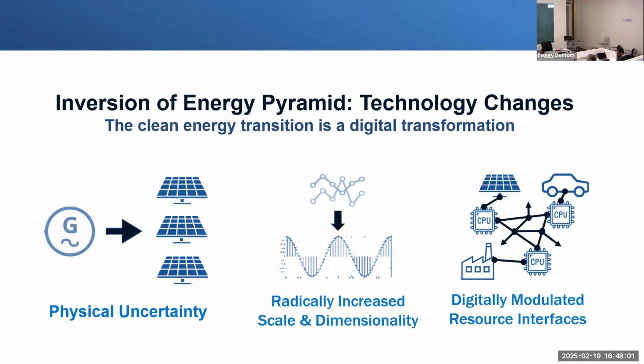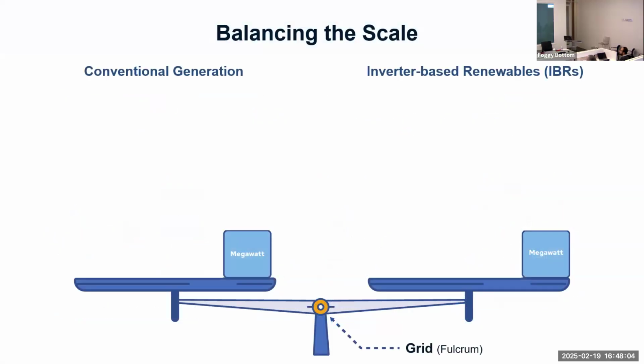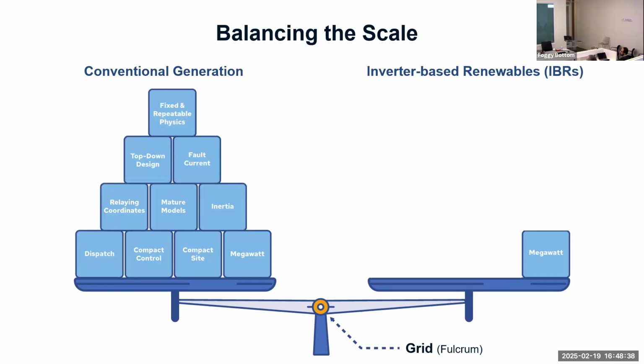So we have both advantages and challenges with those digitally modulated resource interfaces. I don't need to explain this to you since you all have an elevated technical basis, but if this is conventional generation on the scale, and this is inverter-based renewable or any inverter-based resource, a megawatt is not a megawatt. One megawatt over here does not equal one megawatt over here. There's a difference, because with conventional generation I'm not just getting a megawatt, I'm getting dispatchability and compact control—one controller on that 100-acre site controls the whole thing.